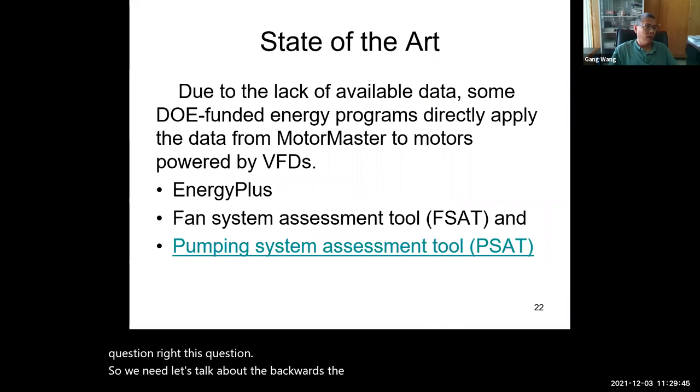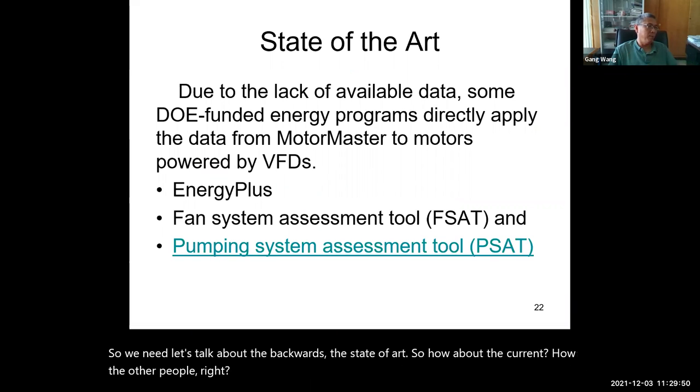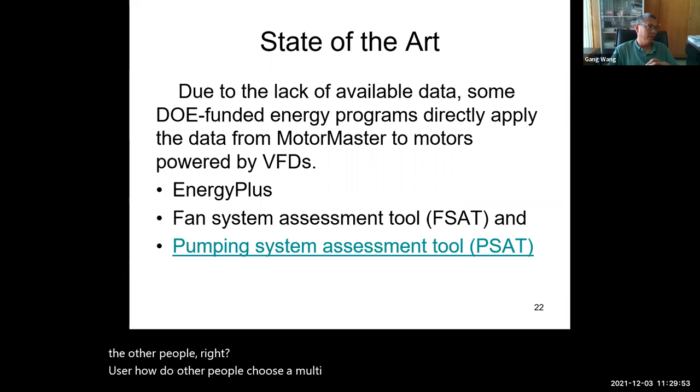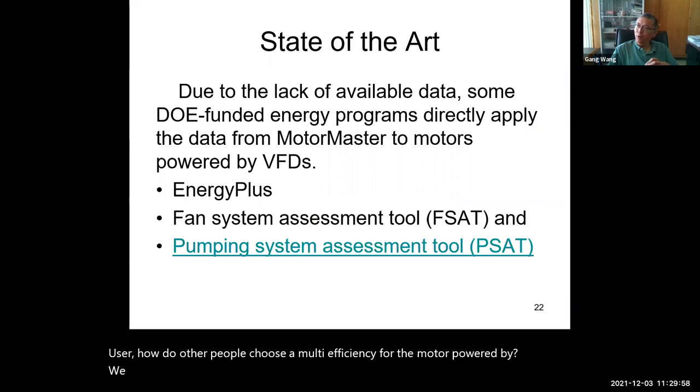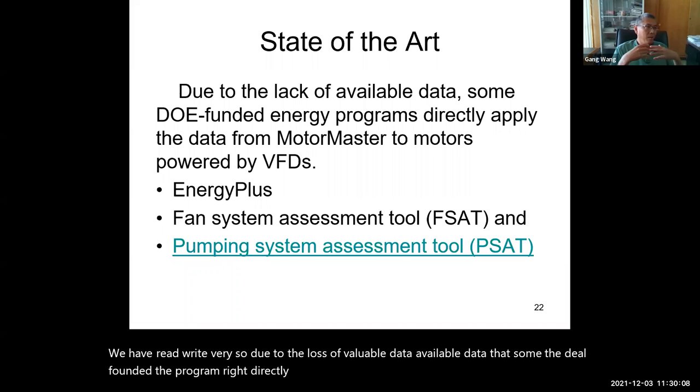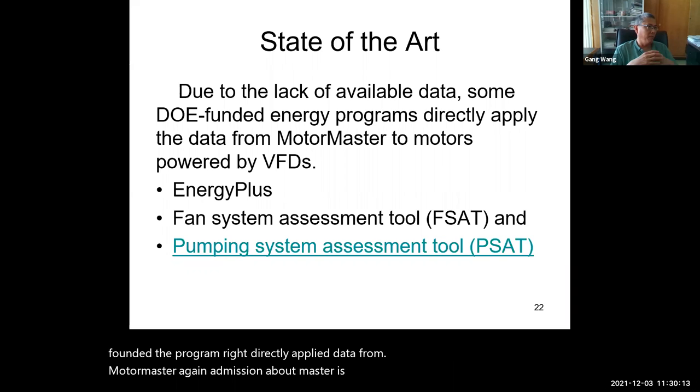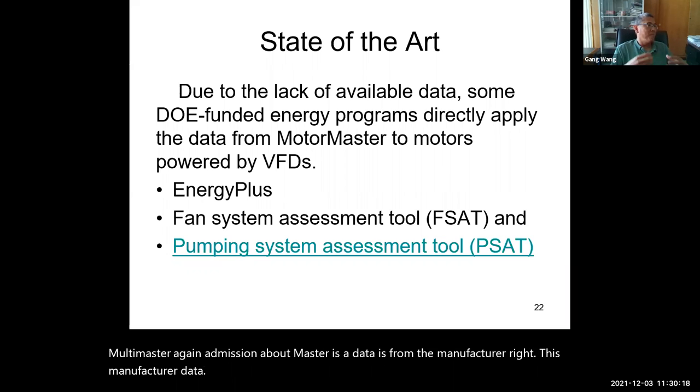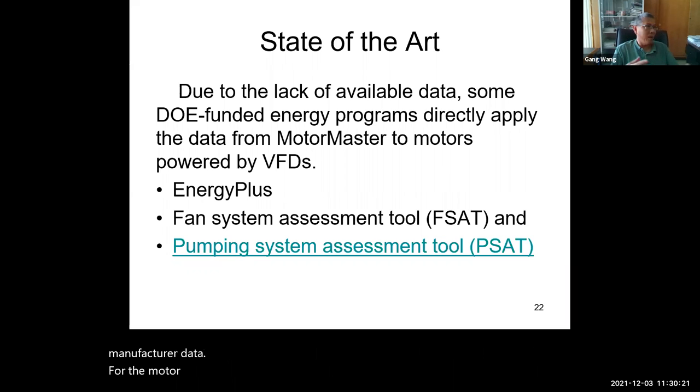The state of the art: how about the current practice? How do other people choose the motor efficiency for a motor powered by VFD? Due to the lack of available data, some DOE-funded energy programs directly apply data from MotorMaster. Again, as I mentioned, MotorMaster data is from the manufacturer. It's manufacturer data for a motor powered by the power grid, not powered by VFD.